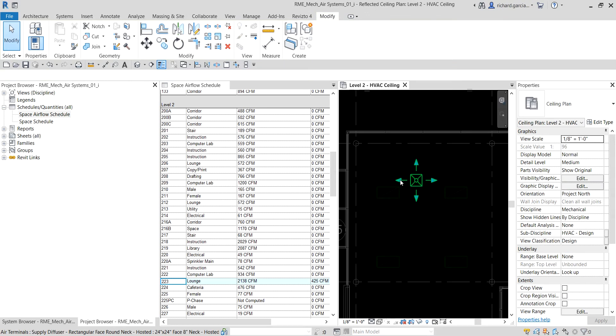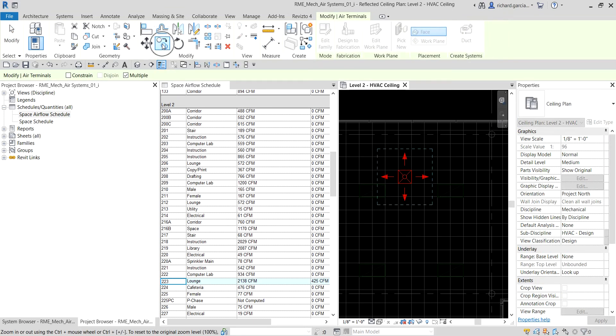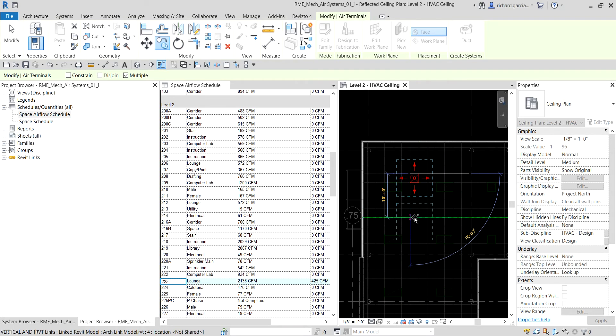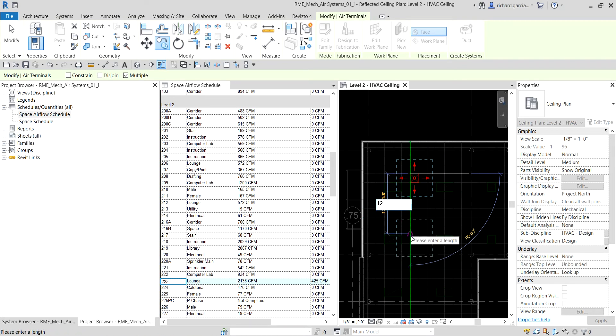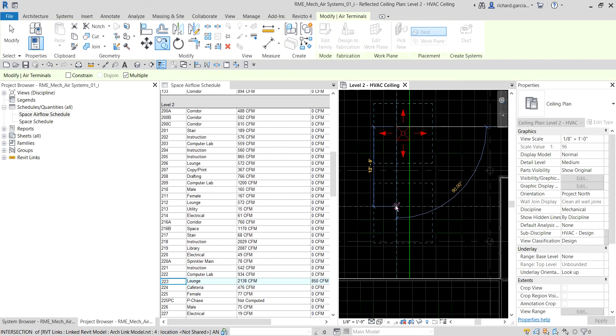I'll select Modify to deselect the air terminal, then click the supply diffuser and choose Copy. Make sure the 'Multiple' option is checked — this allows you to place multiple copies without reactivating the copy tool after each placement. I'll click the upper-left corner, move the cursor down, and type 12 for 12 feet. Revit understands the unit, so no need to type the feet symbol.